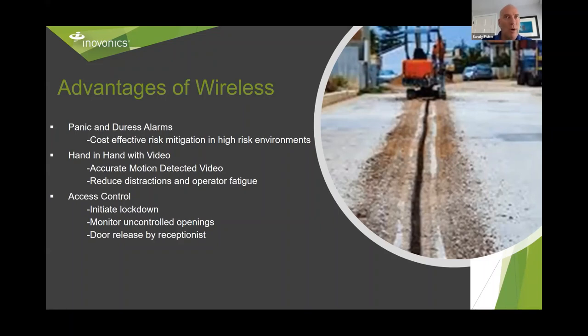Whenever you are hooking up a wireless receiver in that situation, always go into a controller if you can, never directly into the strike, because you don't want that to log as a forced entry.